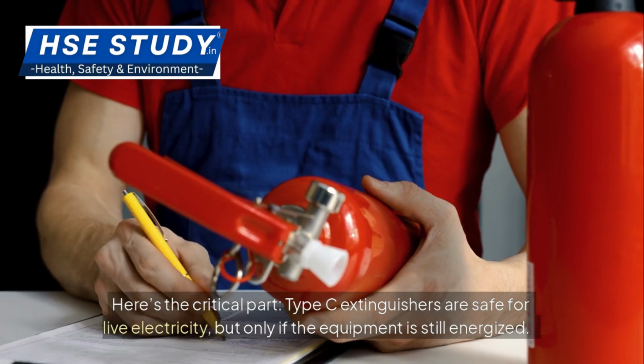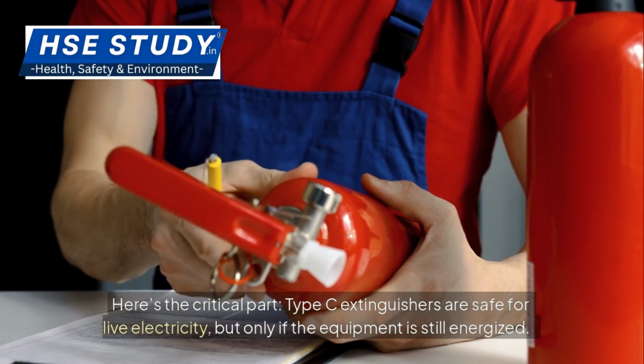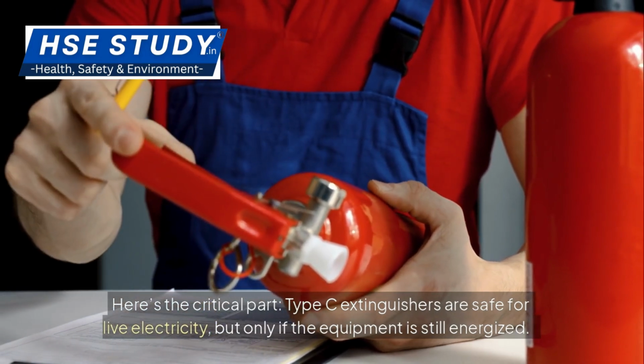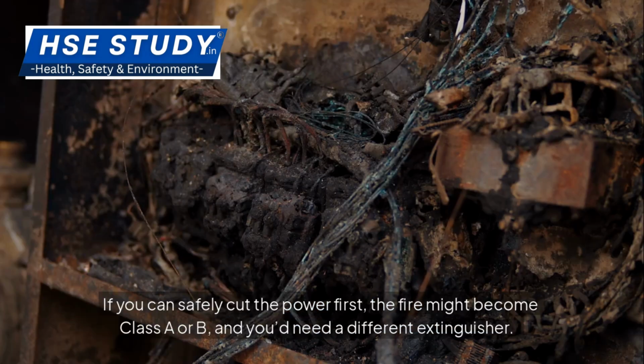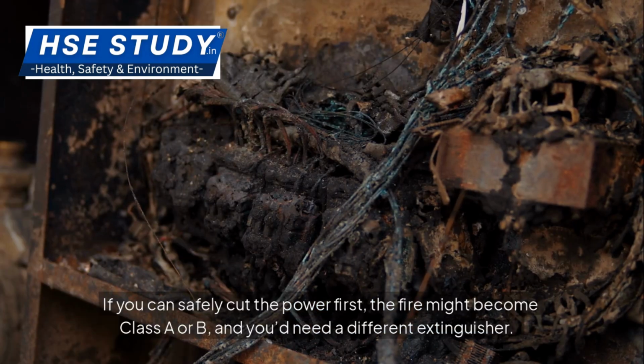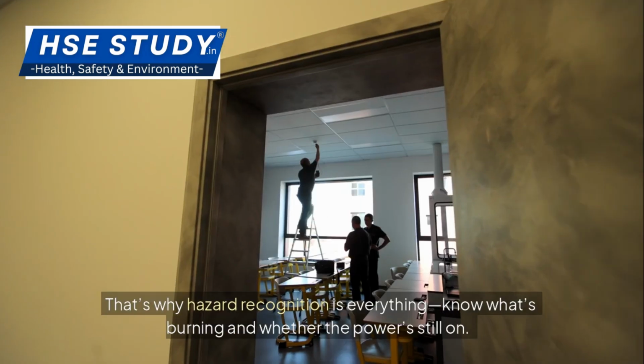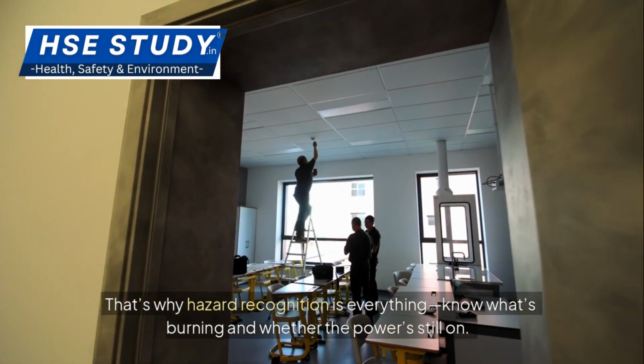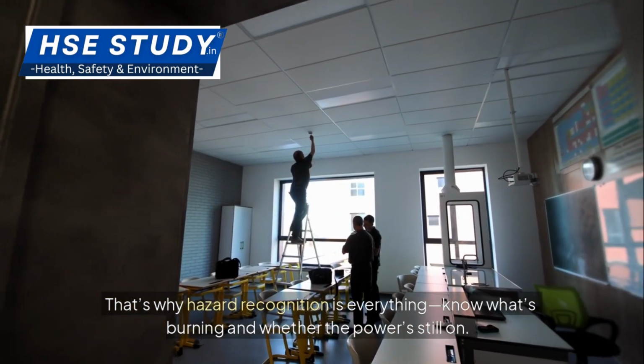Here's the critical part. Type C extinguishers are safe for live electricity, but only if the equipment is still energized. If you can safely cut the power first, the fire might become Class A or B, and you'd need a different extinguisher. That's why hazard recognition is everything. Know what's burning and whether the power's still on.